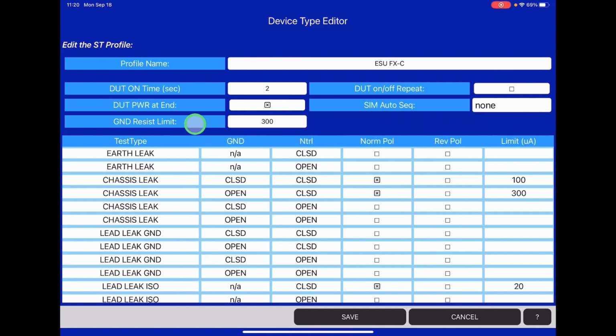And then the ground resistance limit. For this FX-C model, the service manual does not call out for a ground bonding test, a ground resistance test. But for the purposes of this procedure and to be confident that our ground bonding is secure, we're going to go ahead and turn this test on and set the limit as the other ESU analyzers are set to, which is 300 milliohms. So we're going to go ahead and program to do that ground resistance, that ground bonding test.